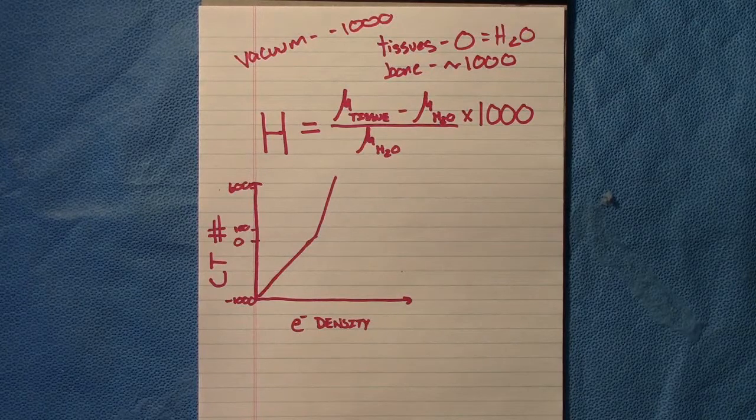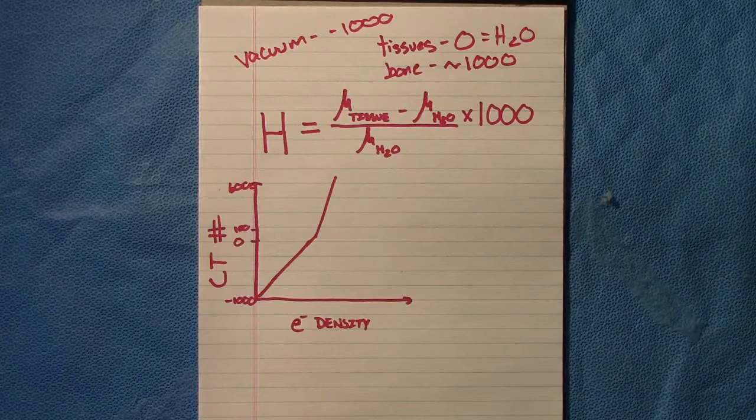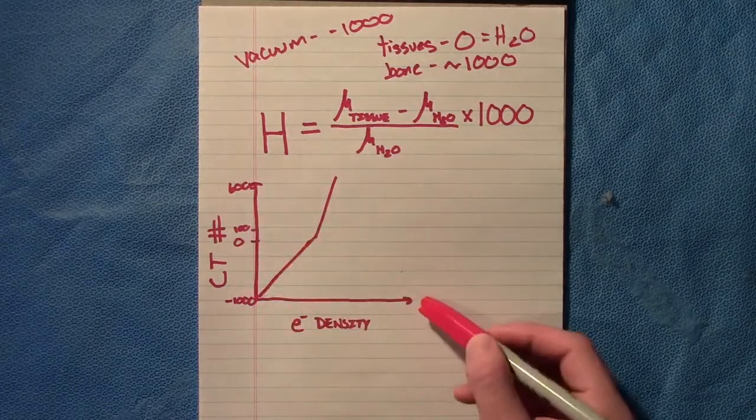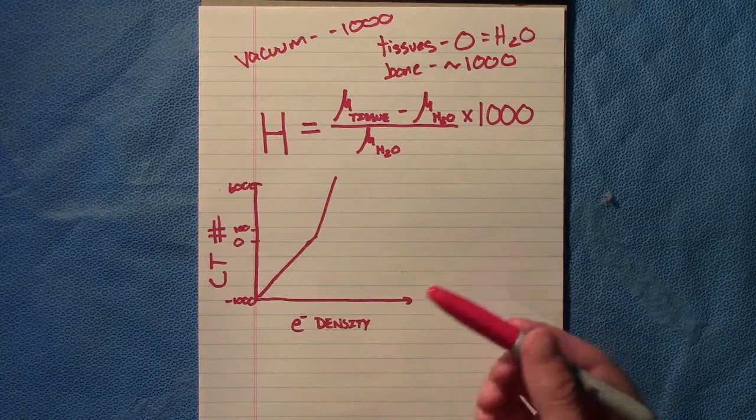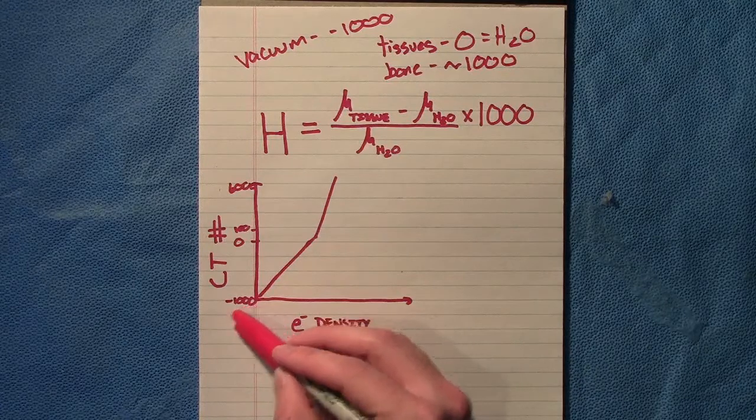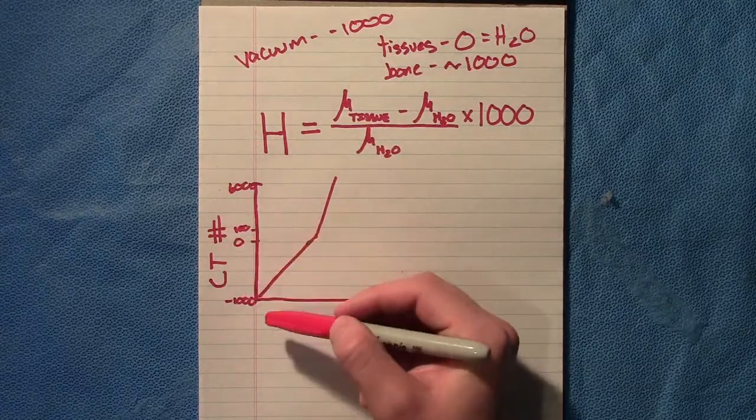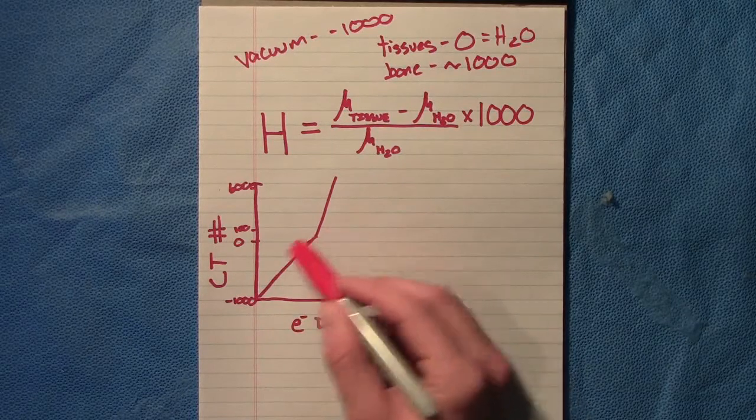For the most part, our CT numbers and our electron densities are linear. So this is a rough sketch of an electron density curve, but the one in your clinic is going to look very similar. From negative one thousand over here on the y-axis, we have CT number from negative one thousand to around zero, maybe one hundred, we're going to have a linear curve.